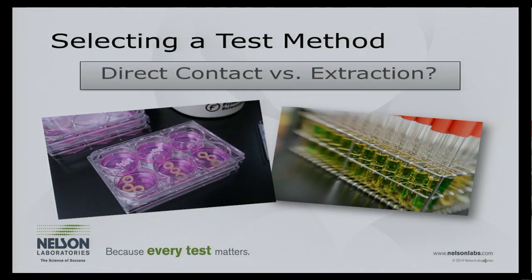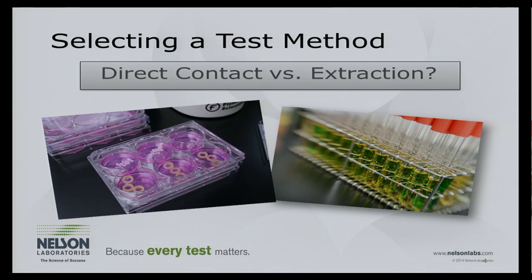When looking at the big three, we need to understand the difference between direct contact and indirect (extraction) versions. For the direct contact test, we put the test sample directly in contact with the test system — directly onto cells or directly onto an animal. For the extraction test, we put the device into a liquid media to make a chemical soup, pulling the chemicals off the device into that liquid, and then use that liquid as the test sample.